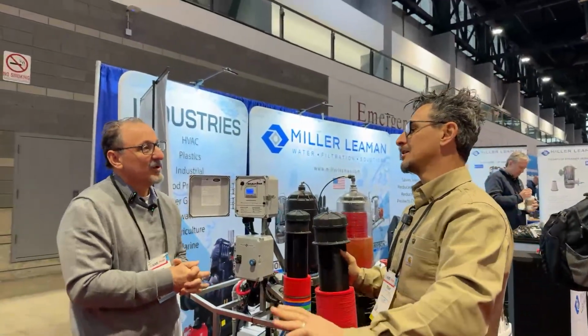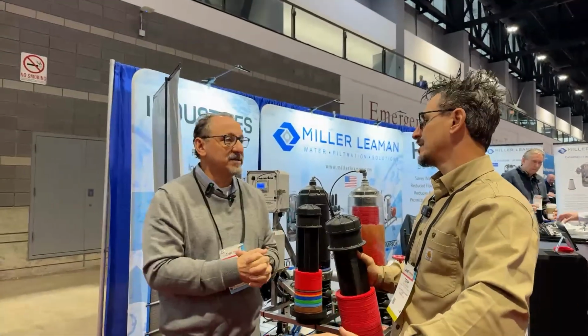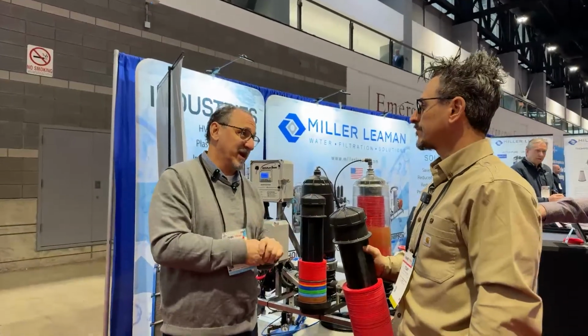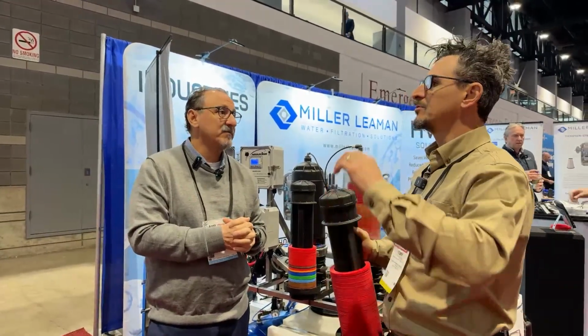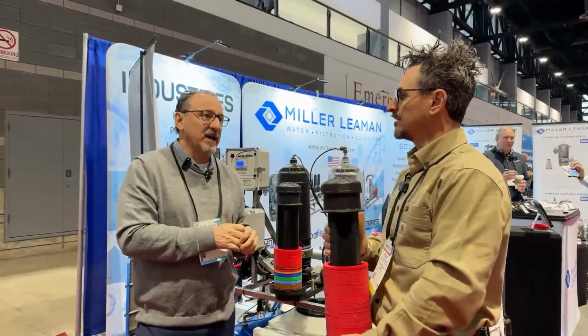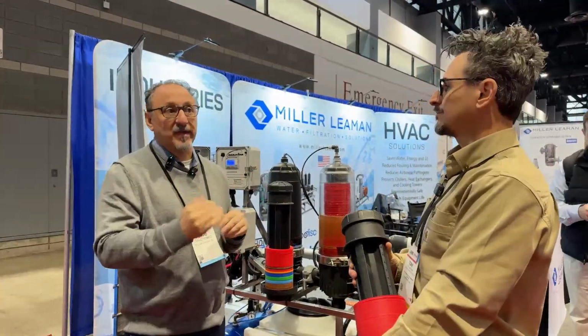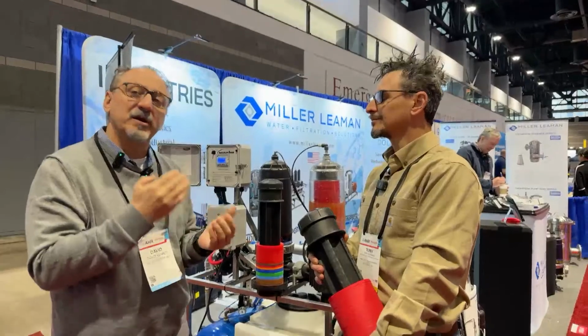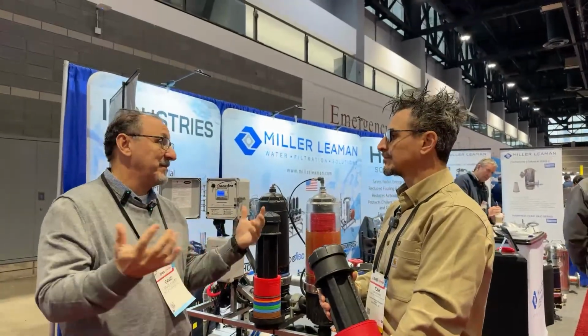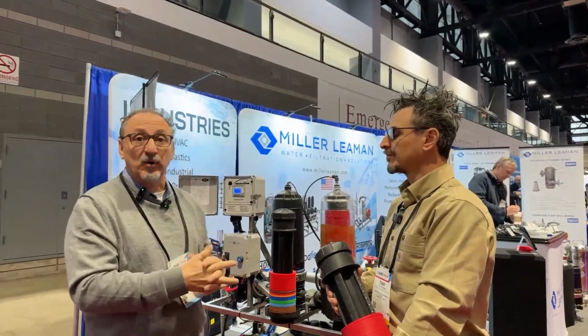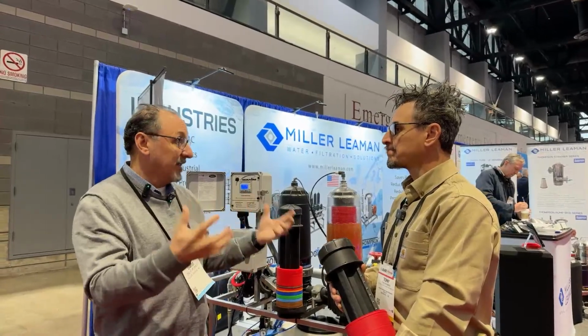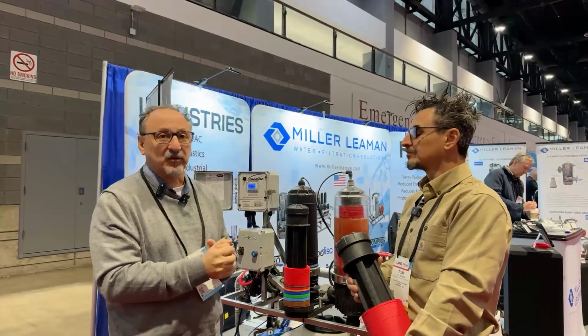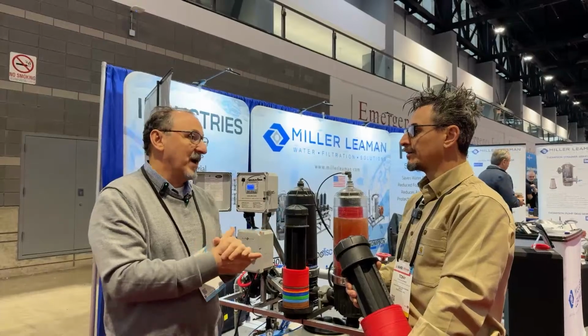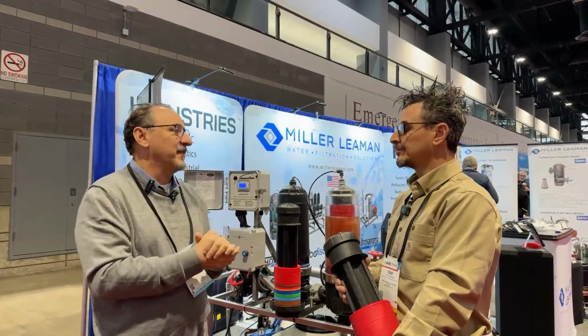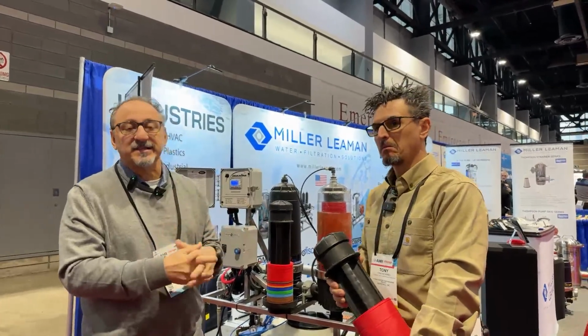That's efficient. So first of all, let's start with the application. Like somebody watching this: cooling tower, side stream, or even full flow in some applications. Even full flow. Exactly. What applications would you typically see? You see a lot of applications where the cooling is so critical that you need clean water downstream. For maybe in the plastic industry, where they're injection molding or extrusion molding, or in situations like that where you really want to protect those molds, you might do full flow. Right. Critical application, chip manufacturing or anything like that, you might want to do full flow. Nice. In a lot of cases, it is side stream.